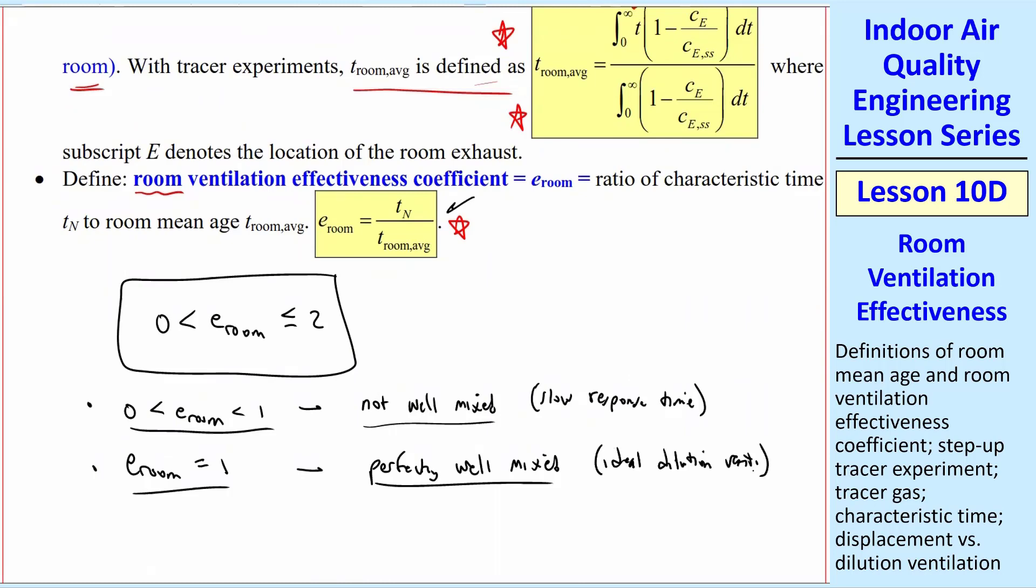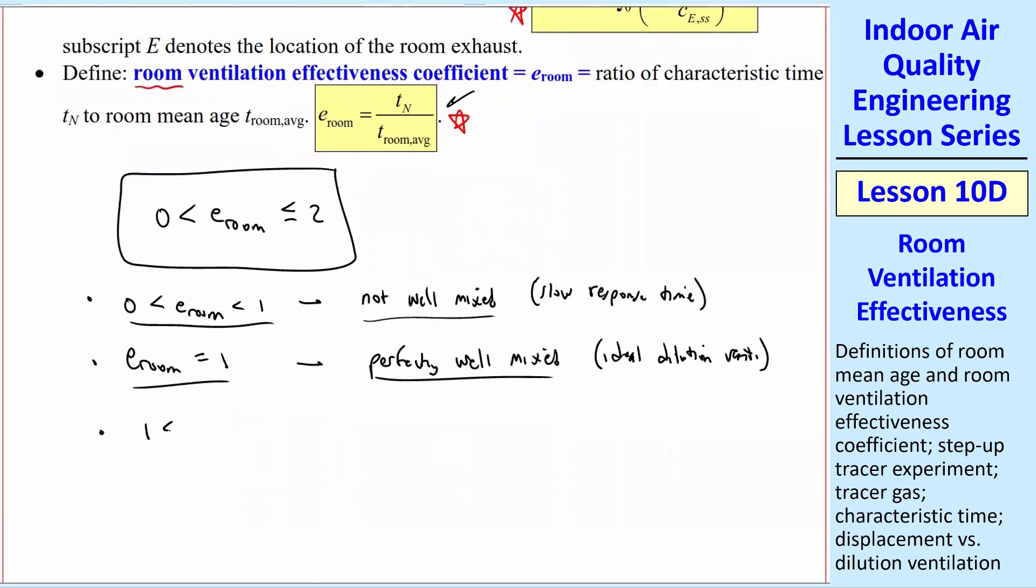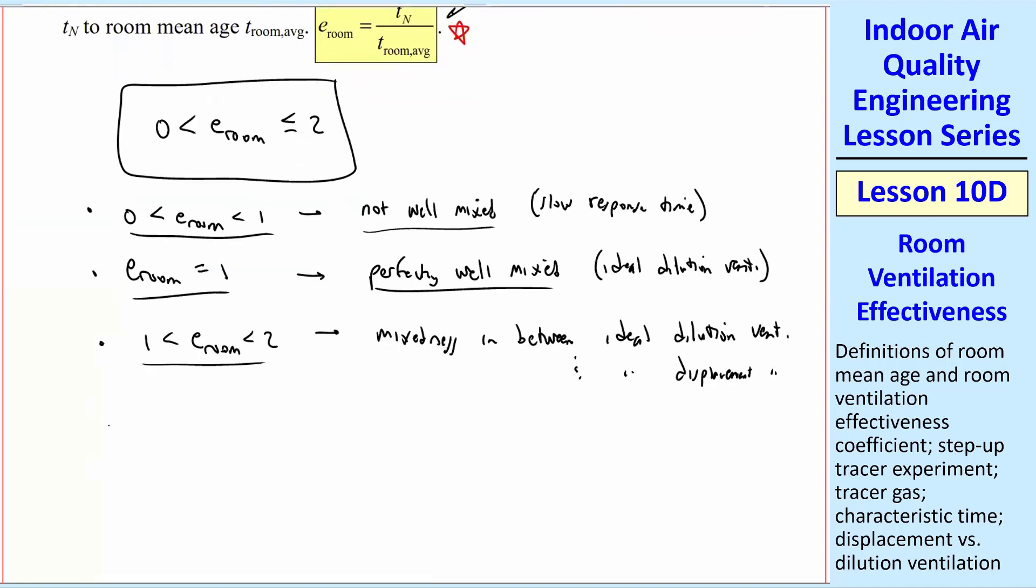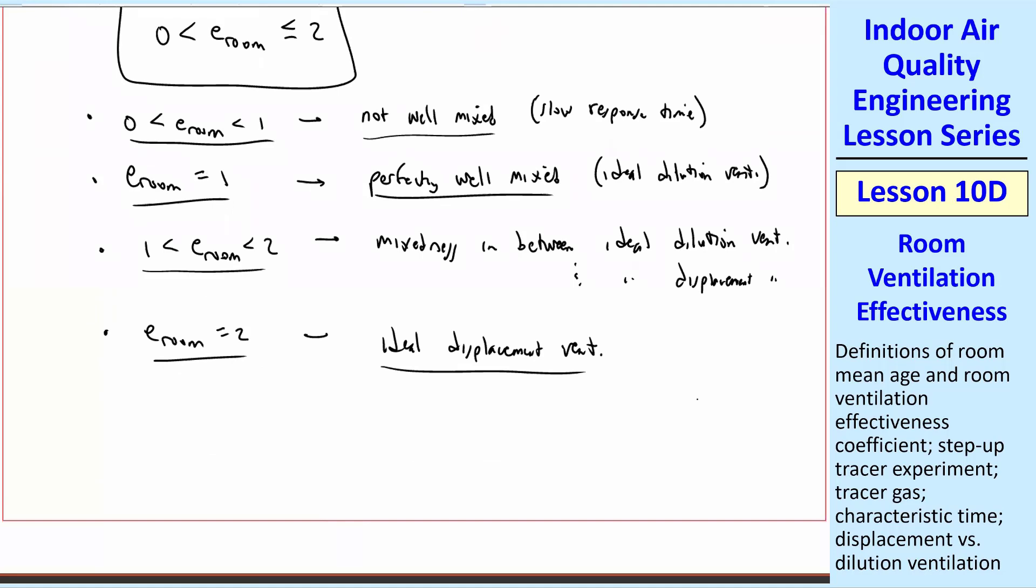As we keep going up, if E room is between 1 and 2, this means that the mixedness is in between ideal dilution ventilation and ideal displacement ventilation, somewhere in between the two. And then finally, when E room is equal to 2, this is ideal displacement ventilation. Ideal displacement ventilation is kind of tricky because it has perfectly well mixed in the part of the flow that's been influenced by the inlet. And then it's pushing out that stale air. And we're going to deal with that one as our example, actually. So you'll see this in more detail. So those are the possibilities.